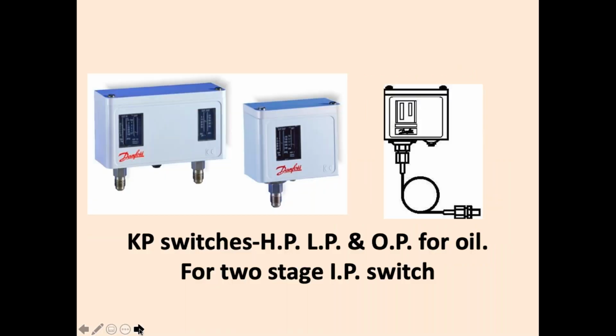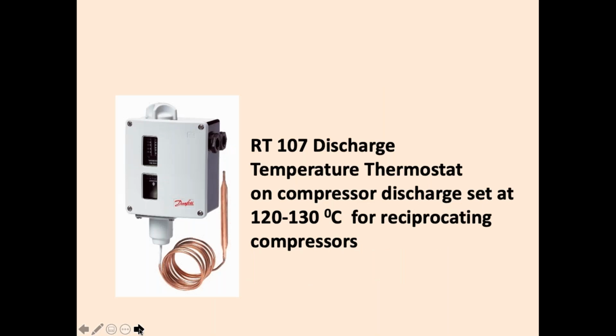These are the pressure switches. Use all of these pressure switches: HP, LP, OP, and for a two-stage compressor, the intermediate pressure switch. These are all important pressure switches. Don't bypass them. They are all safety switches. For high discharge temperature on the compressor side, use this. I use it in my plants and it helps a lot.